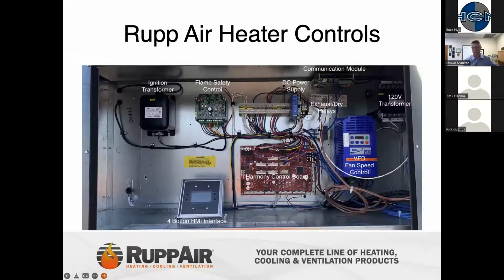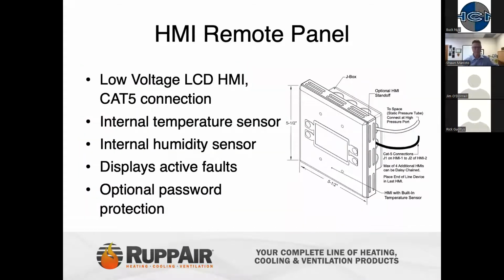So one thing about our industry is our industry was basically very slow to adopt. You're still seeing a lot of manufacturers using some of those 1970, 1960 type components. This is kind of just bringing it to today's technology. Having easy to use remote interfaces for the operators. Simple Cat5 connections, very simple to install, no longer having to run 15 wires from a makeup air system down to a control panel, but rather just have a single Cat5.